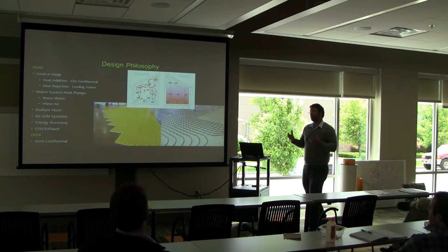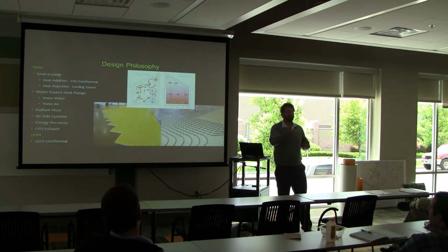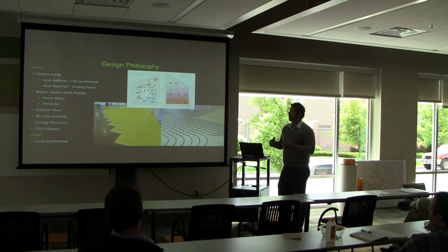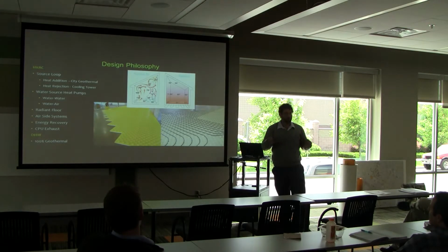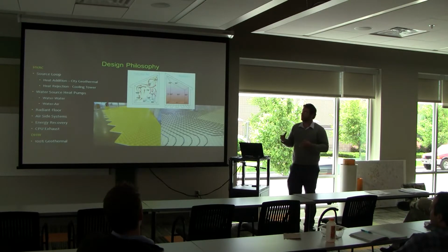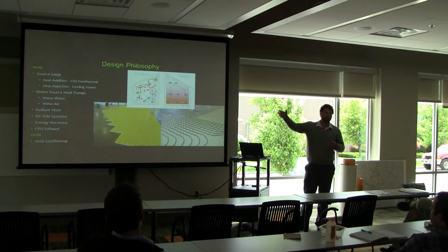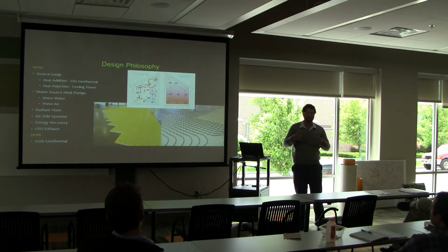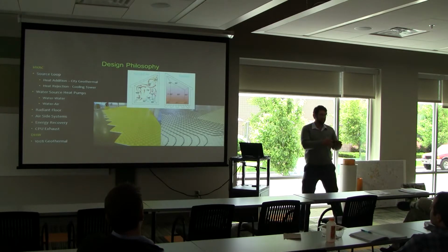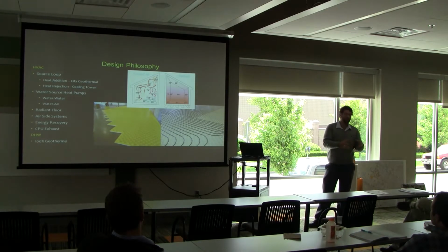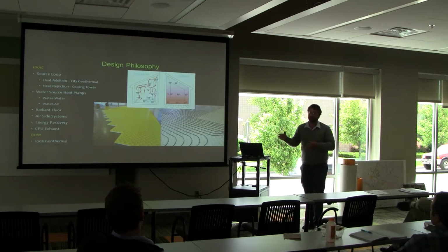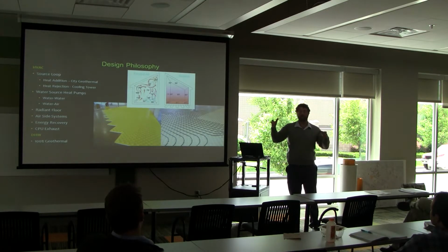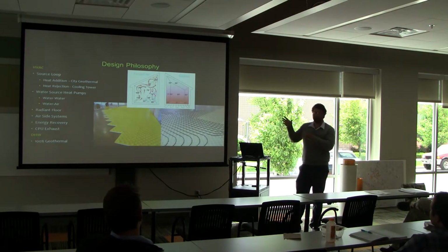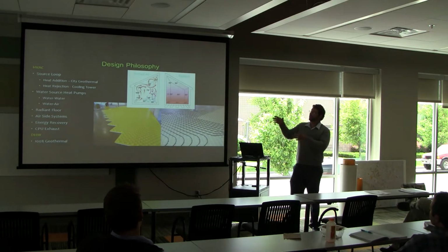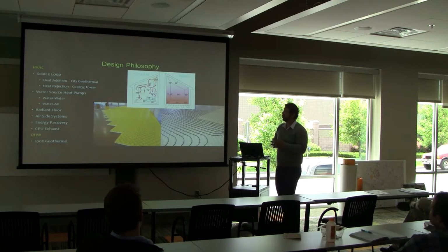You might ask, well, if we have 160 degrees, why don't we use it directly in the floor? There are zones where Russ did design that in, where we're using that directly. However, using heat pumps on what's called a source loop allows for a certain bit of redundancy. So if, God forbid, the supply line gets colder than 160 or goes out for a day or two, we're not completely sunk. We can still heat the building accordingly. So it's not that we couldn't, or Russ couldn't have used it. They just use it as that redundancy point.